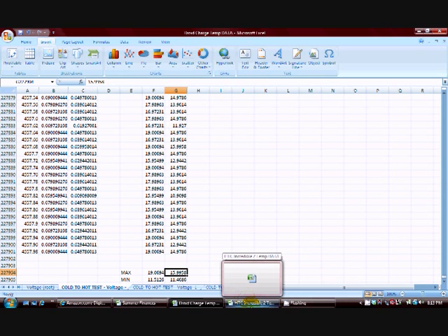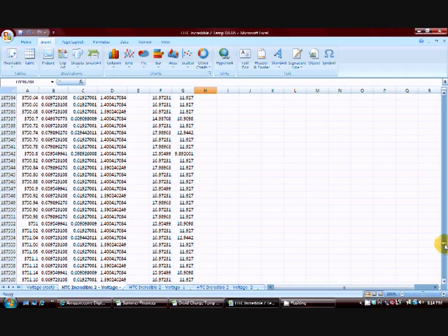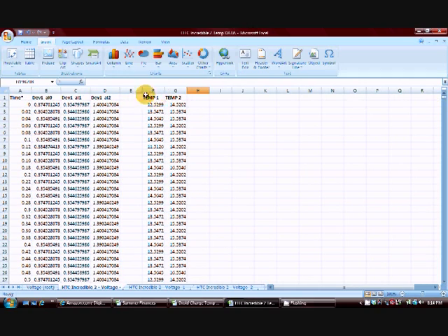We're going to go ahead and take a quick look at our second commercial phone. Once again, your temp sensor 1, which corresponds to the AI0 voltage data readings, is the temperature sensor on the inside of the phone, and the temp sensor 2, which corresponds to AI1, corresponds to the outside temperature sensor. Please note that the AI2, I wanted to add that as a constant for this test, just to make sure that we had some good temperature sensor readings.